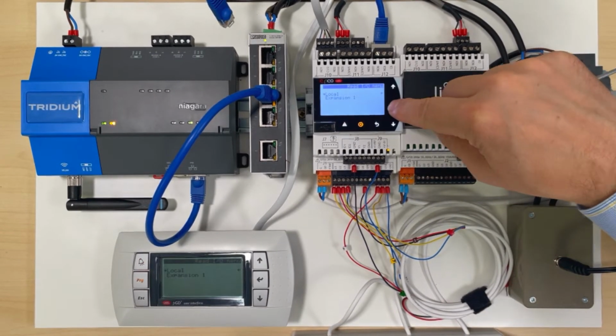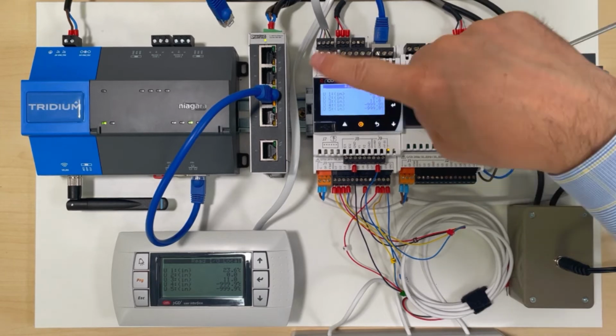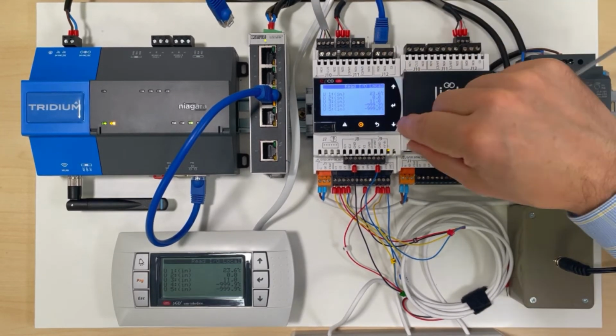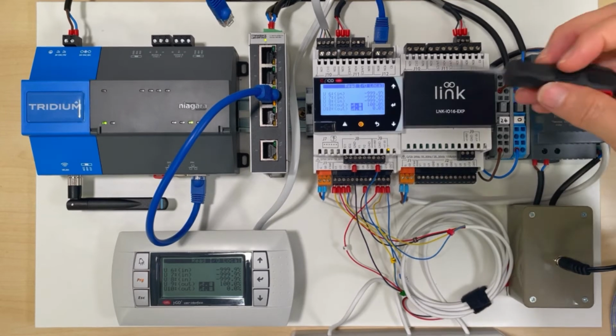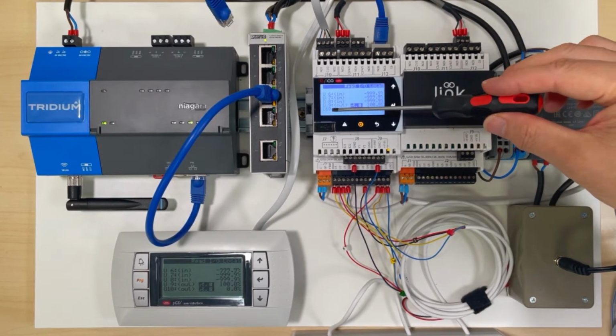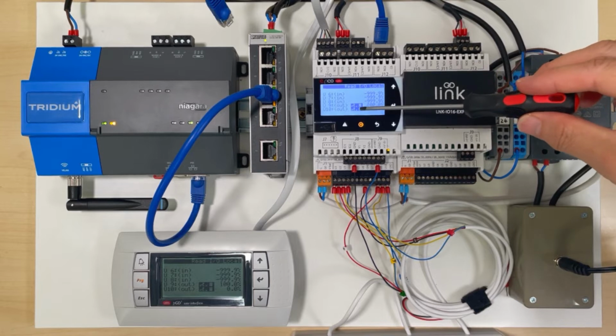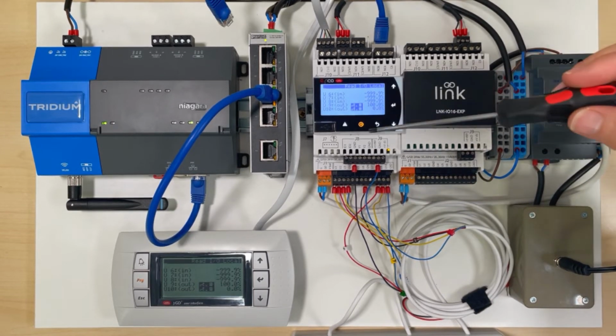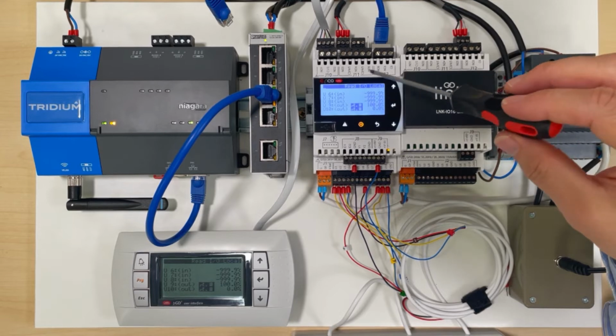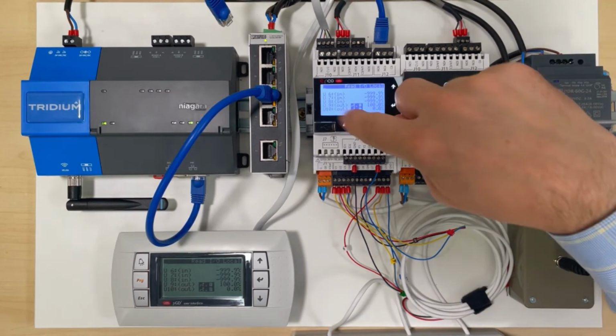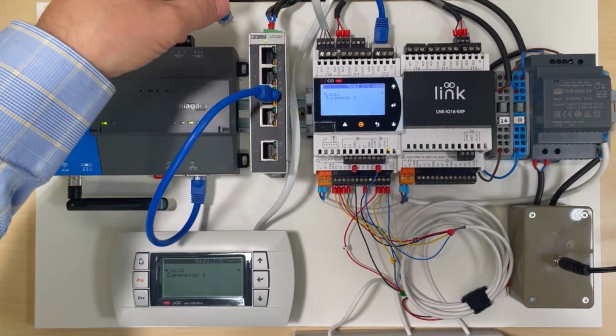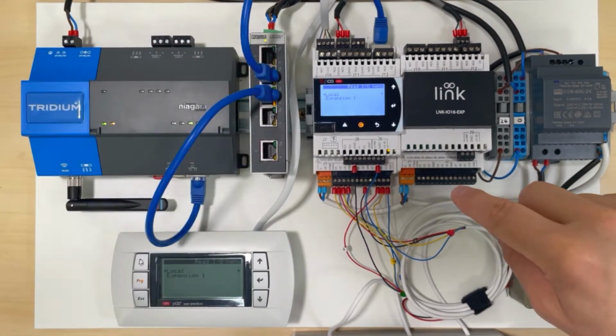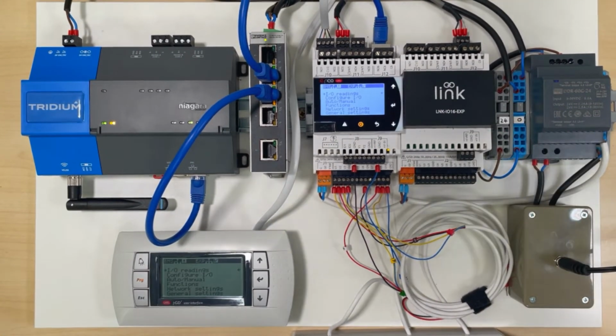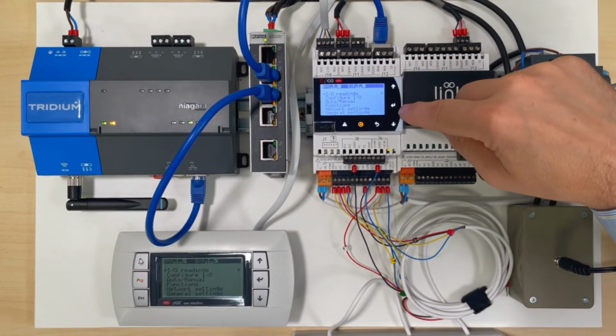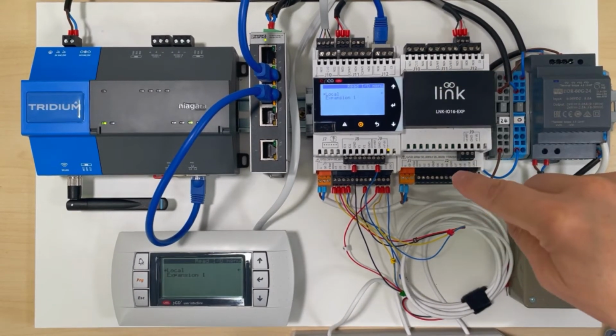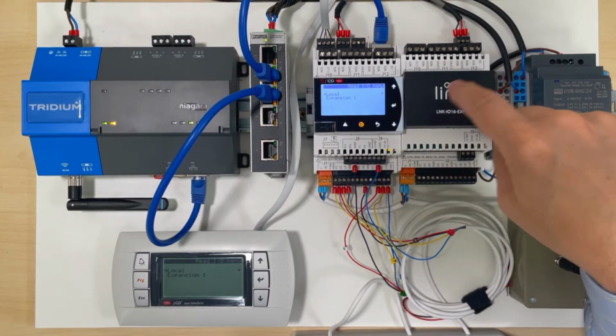Now if we go into the IO readings, you'll notice it gave me the option of the local or the expansion. I'm going to concentrate on the local. If we look here, on 9 and 10, they're set for a watchdog function, and the little flag comes up to show you that indeed the watchdog function has kicked in and has set it to 100%, 0%. Okay, so let's put the BMS back in and give it a little while to clear. If we go back to the main menu, we'll see that flag clear. All right, so let's have a look at the IO readings menu. So we select local, this is a local one, this is an expansion one.